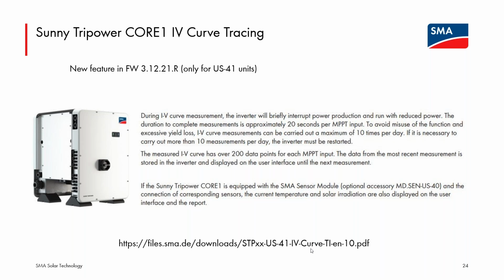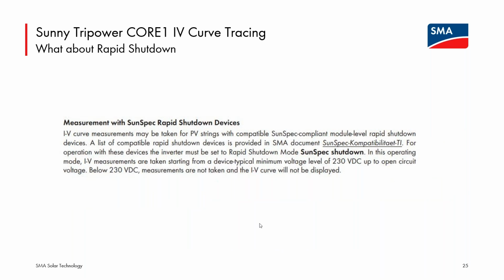So this is the location of the technical document that talks about the curve tracing. This is on the website on the product page for the CORE1 right now. This will work even if the array is equipped with the SunSpec rapid shutdown devices. The thing is, if you drive that IV curve from all the way from VOC down to 0 volts, lower voltage, you'll begin turning off those rapid shutdown receivers.